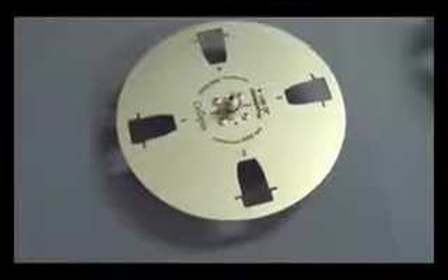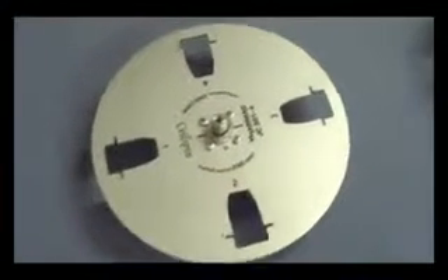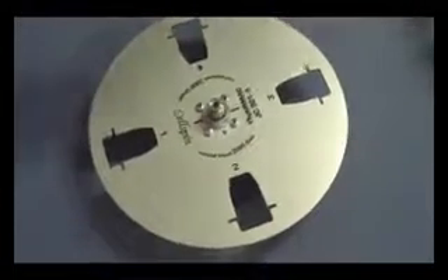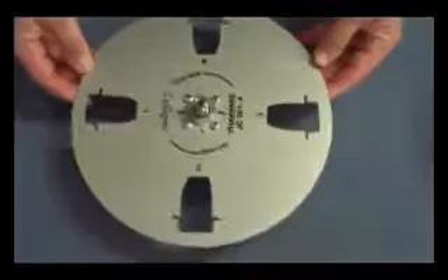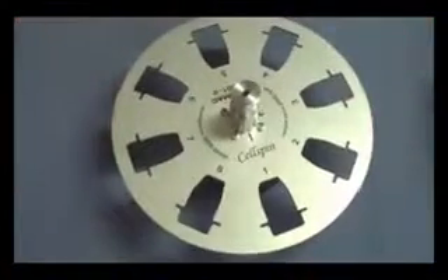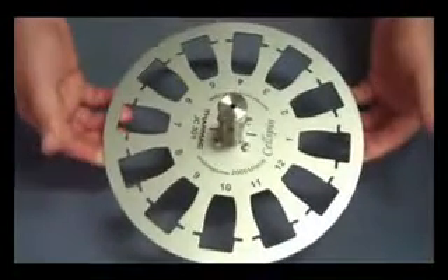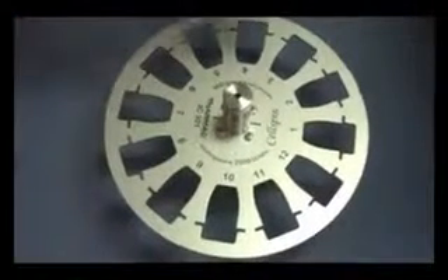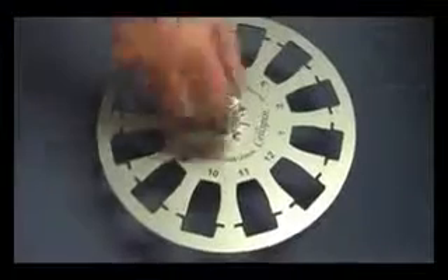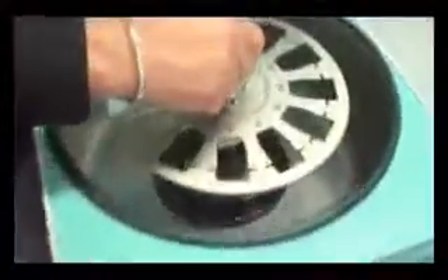For the Cellspin cytocentrifuge, we have 3 different types of rotors which we can attach to the machine in 3 different ways. To give you the choice and to be able to give good prices to your customers, you can choose a 4-position rotor, which is this one here. A little bit more expensive, you have the 8-position rotor, and here is a 12-position rotor, which is a workhorse. This 12-position rotor is a removable rotor. That means you can take it into the machine and take it out of the machine.